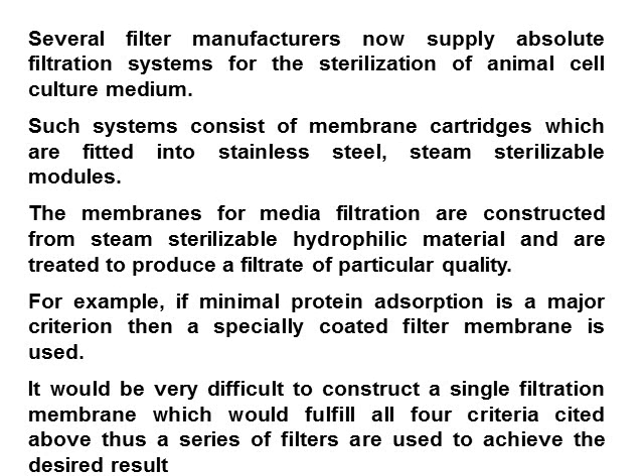Several filter manufacturers now supply absolute filtration systems for the sterilization of animal cell culture medium. Such systems consist of membrane cartridges fitted into stainless steel, steam-sterilizable modules. The membranes for media filtration are constructed from steam-sterilizable hydrophilic material. For example, if minimal protein adsorption is a major criterion, a specially coated filter membrane is used. Since a single membrane cannot fulfill all criteria, a series of filters is used to achieve the desired result.